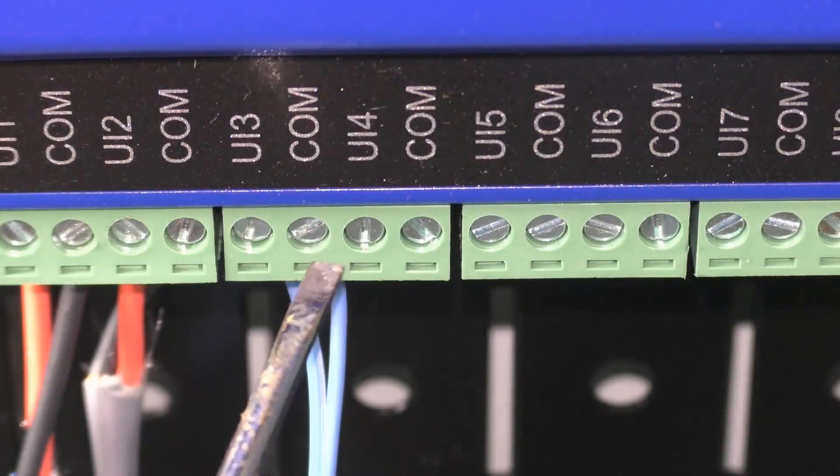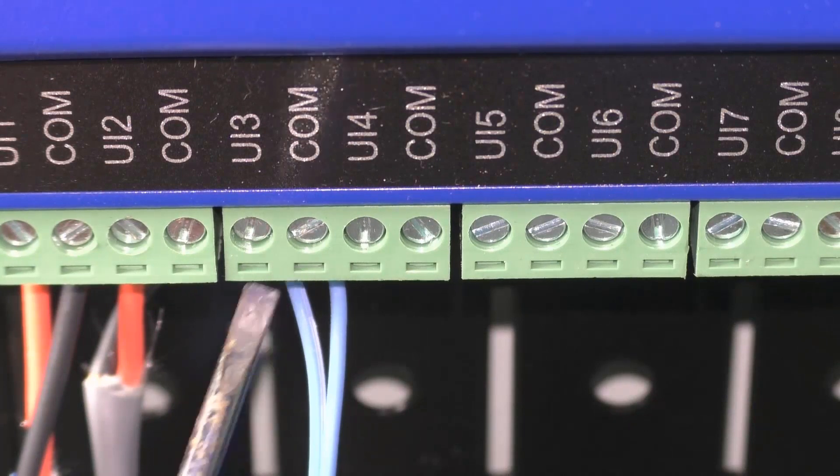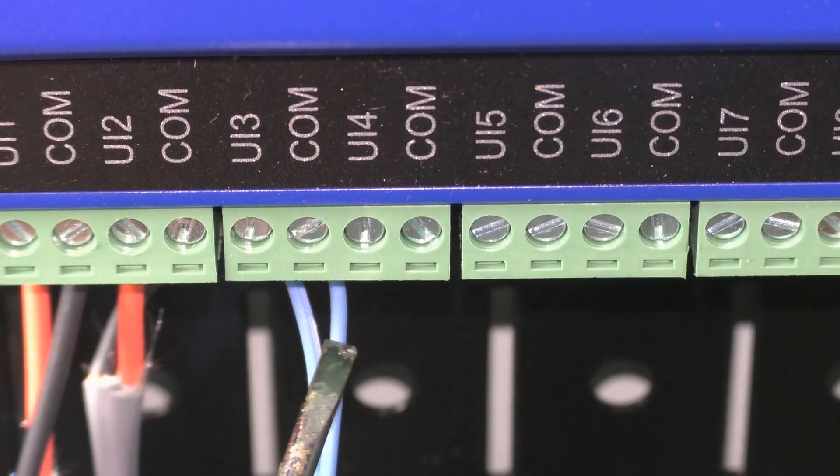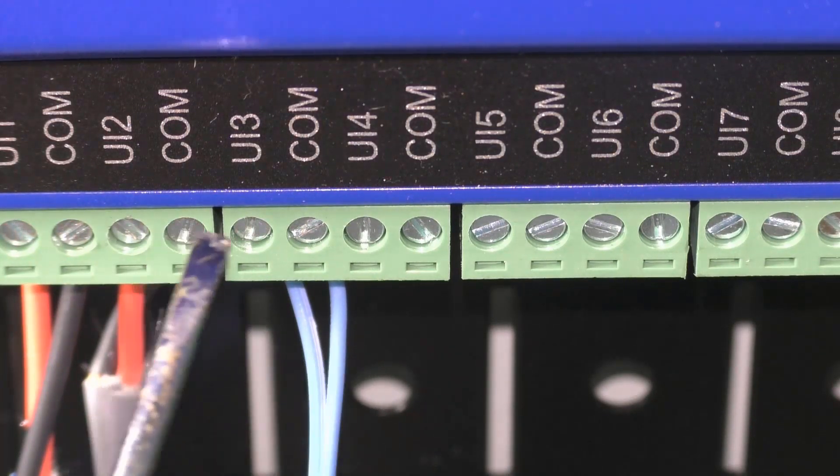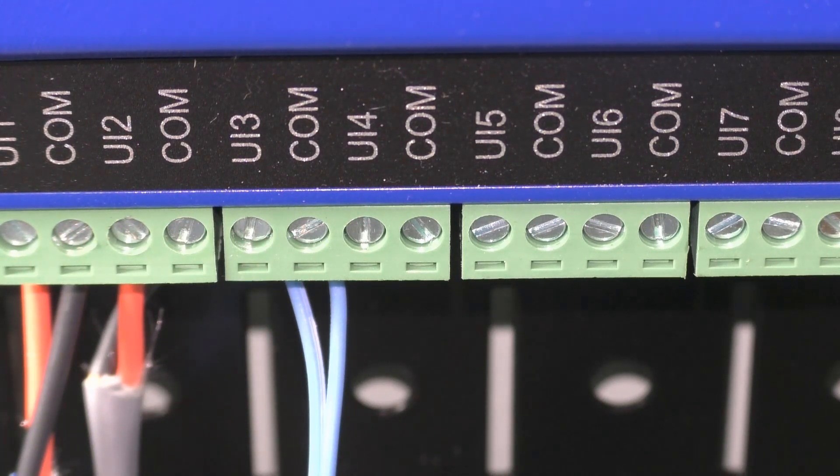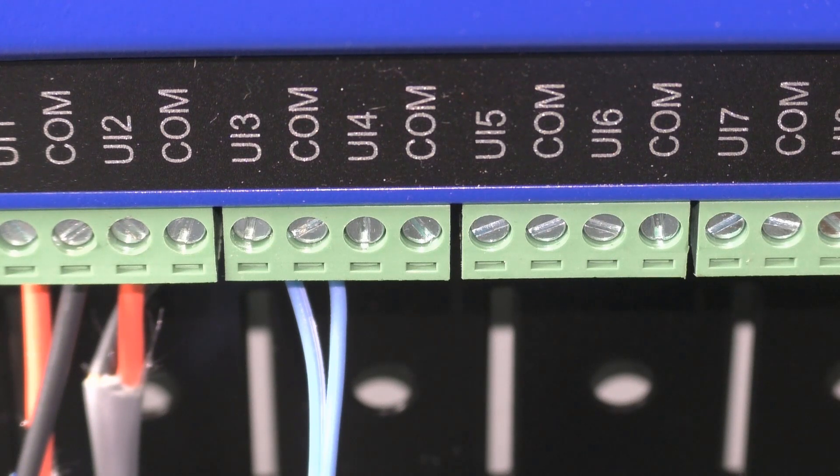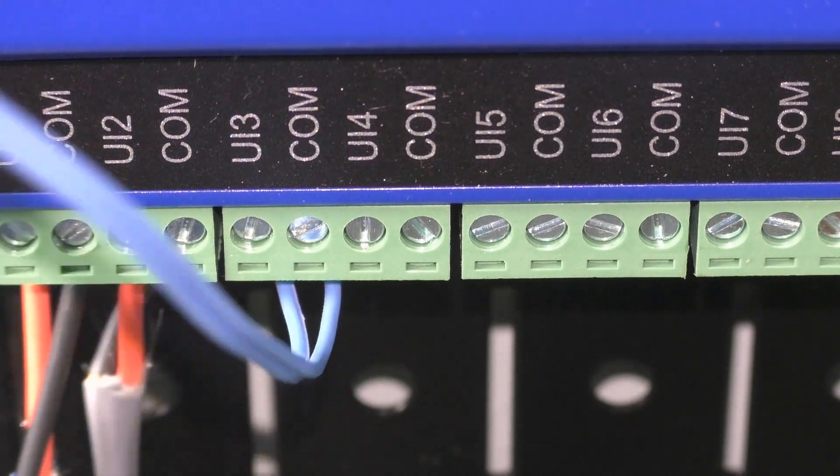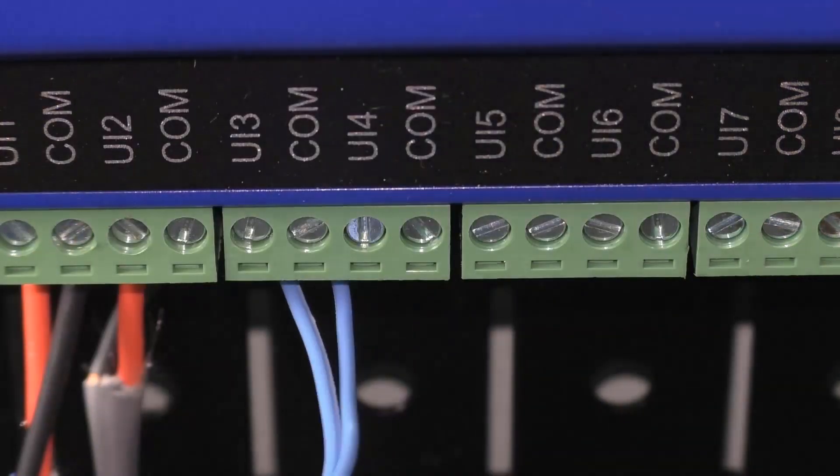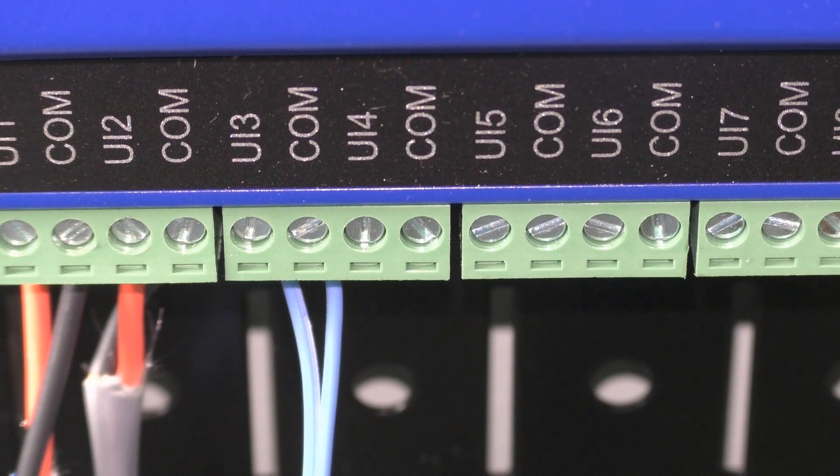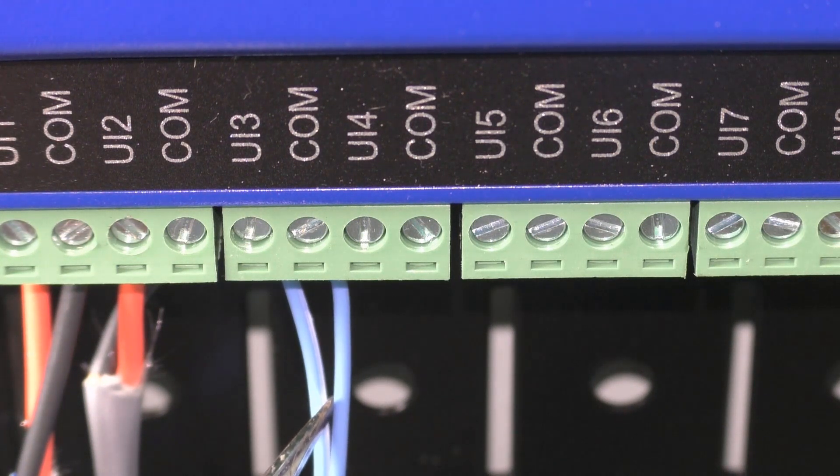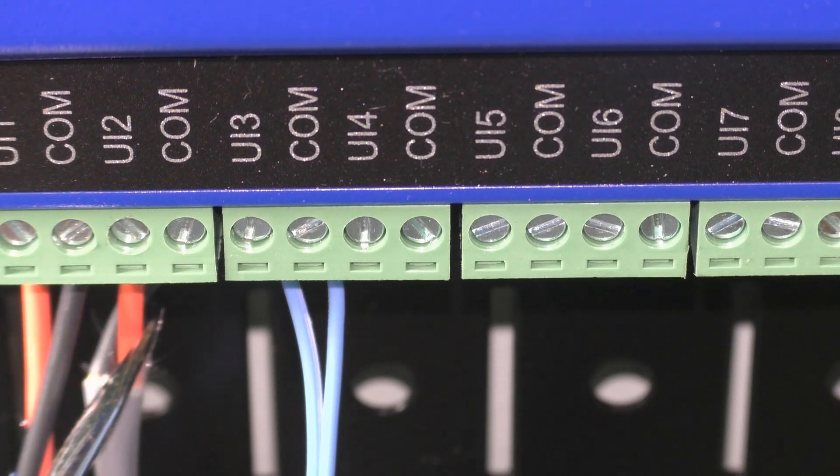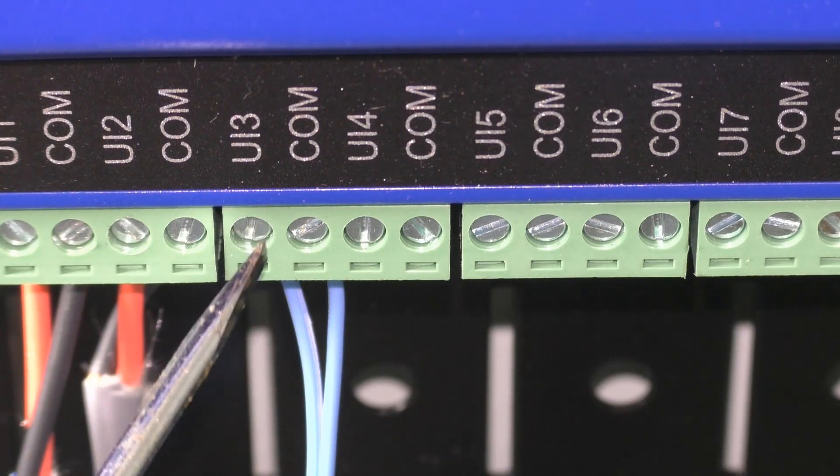Now as you can see on UI3 right here, we have our leads from our sensor terminated into the terminal block. Something you need to be careful about when dealing with temperature sensors or most inputs in general, if you are using the wire directly like we are, typically the wire will be very thin. You can see it's a very thin wire compared to this much thicker wire over here.